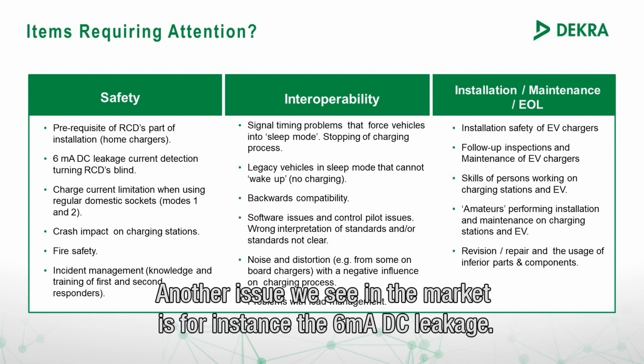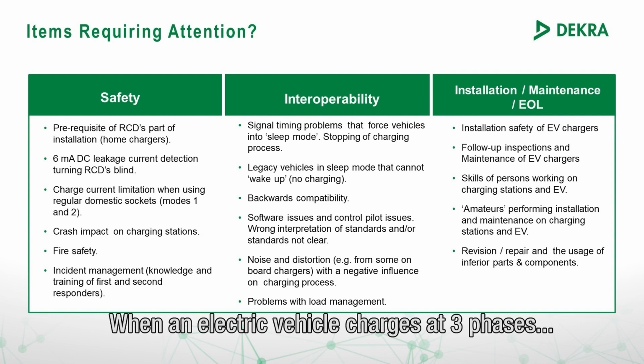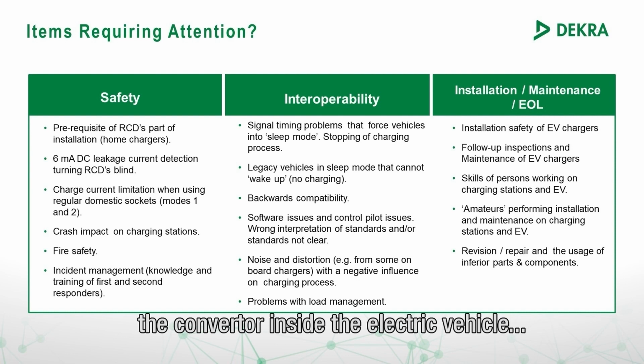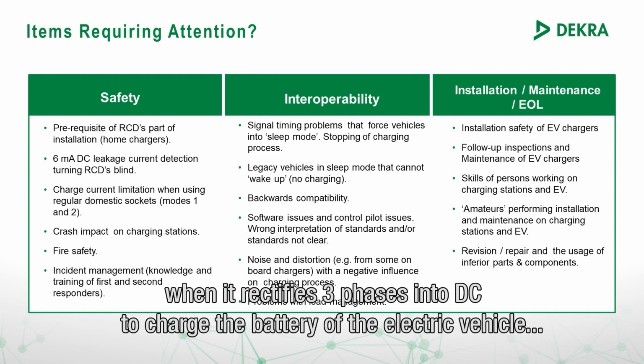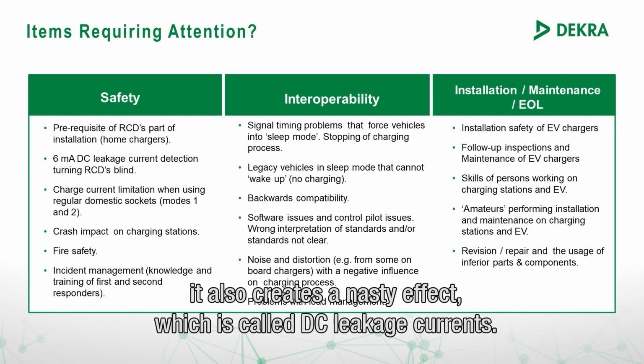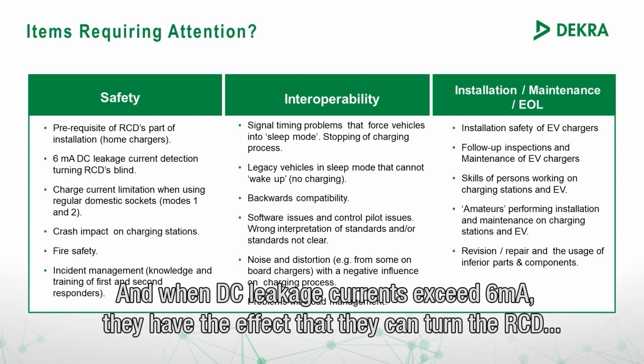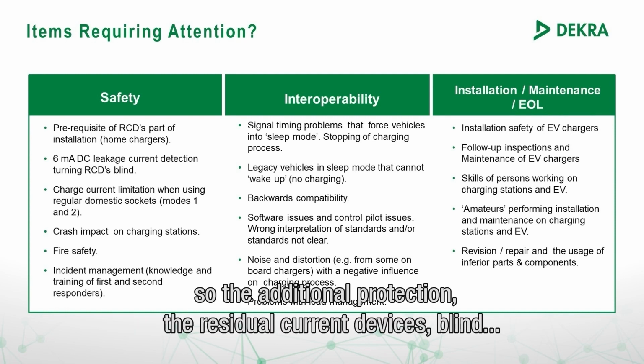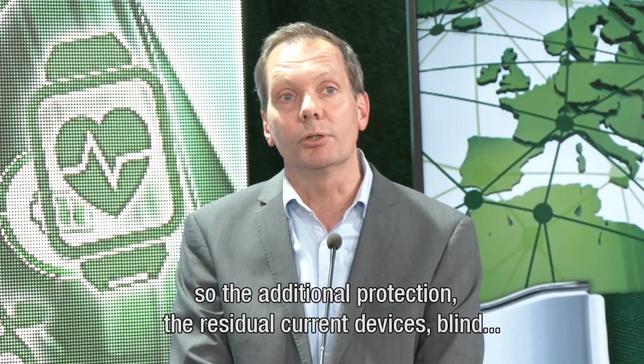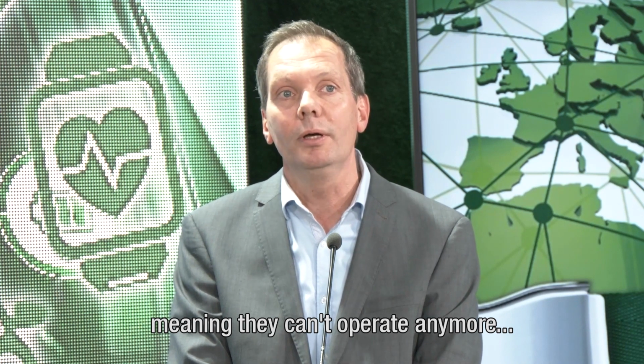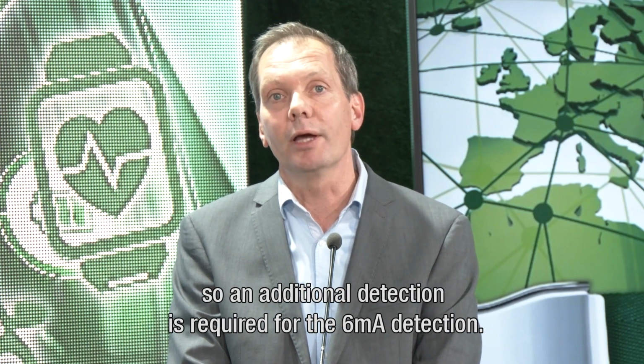Another issue in the market is the 6 milliamp DC leakage. When an electrical vehicle charges at 3 phases, the converter inside the vehicle rectifies 3 phases into DC to charge the battery, which also creates a nasty effect called DC leakage currents. When these go above 6 milliamp, they can turn the RCDs - the residual current devices - blind, meaning they cannot operate anymore. So additional detection is required for the 6 milliamp detection.